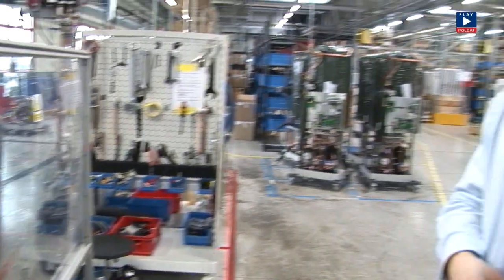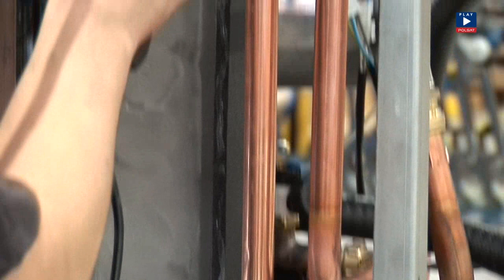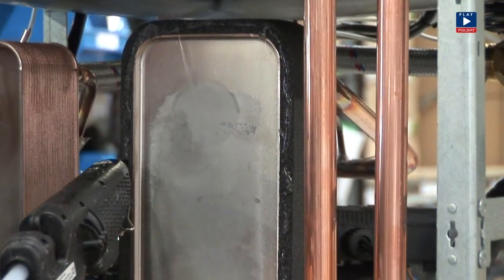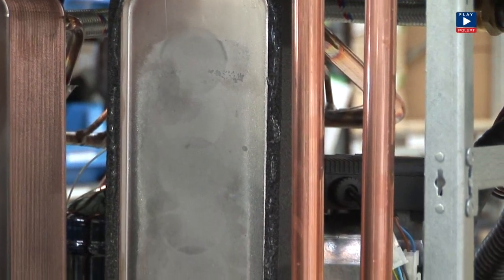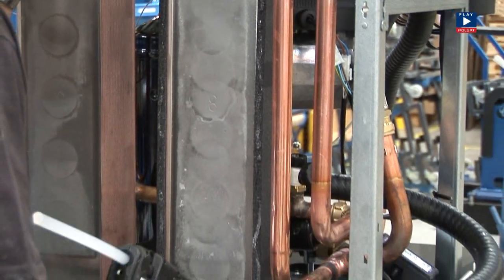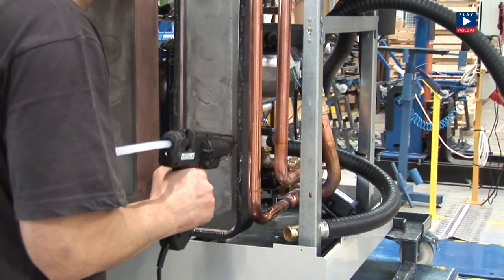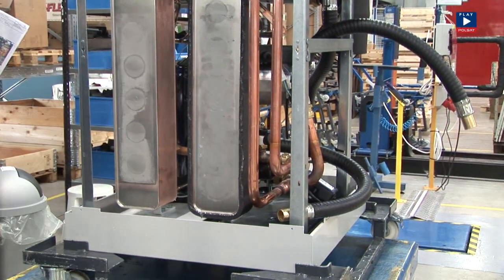The functional test is the main element in examining the heat pump. During such a test, we adjust each parameter of the pump and make sure that all components used here meet quality and energy saving requirements. In the pump, despite the fact that it generates heat, the majority of the processes operate at temperatures close to or below 0 degrees Celsius. And that is why one of the factors we have to eliminate is the vapor condensation effect on the pipes.